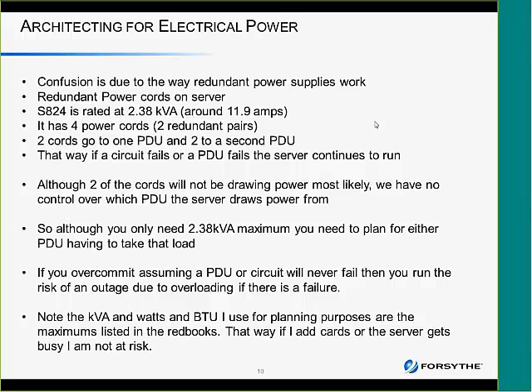So because we have, A, no control over which PDU it draws from at any time, and secondly, if a PDU fails, it will draw from the other PDU, we have to plan out as if we were going to be using full power on both PDUs at the same time. So that's one of the reasons why, even though you say to me, well, I'm only really drawing 2 kVA, but you're making me plan for 2.38, and you're making me plan for it on each of 2 PDUs, that is the reason why. Because if you overcommit, assuming that a PDU or a circuit will never fail, you run the risk of an outage. Additionally, we don't actually know which PDU it's going to draw from.